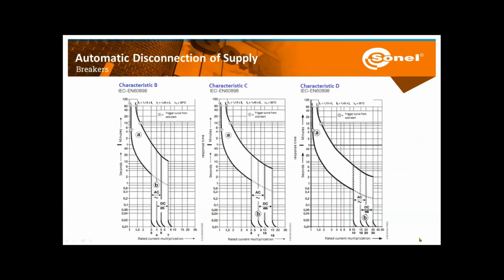Okay, now what is going to make them disconnect in this time? Well, obviously the current. So let's look over here. We have characteristics of different breakers. Let's look, for example, at characteristic C. Here we have time, seconds and minutes, and here we have the multiplication of the rated current of our safety device. So let's look at MCB type C for 0.4 seconds over here. The multiplication for an AC network, the multiplication of the rated current is between 5 and 10. So, for example, if we have an MCB C16, then the disconnection current that will make the MCB work within 0.4 seconds will be 10 times 16. So for C16, 160 amps will be the disconnection current.